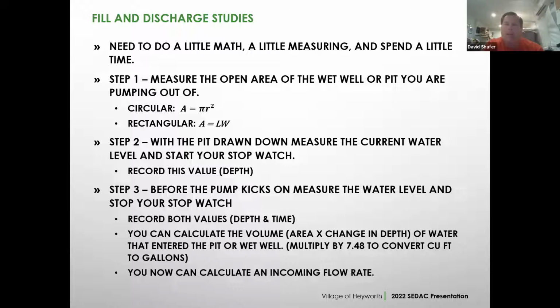Then I'm going to come back before I get to a pump on point, measure the water level and stop my watch. So I started at 12 feet, and now the water level's up to 8 feet. I had 4 feet of depth change, and say that took 10 or 15 minutes. Now I have a volume because I have a depth and an area, and I have time. So I can figure out how many gallons came into this pit. If you want to work in gallons, you need to multiply by 7.48 to convert from cubic feet to gallons. That gives you an incoming flow rate.